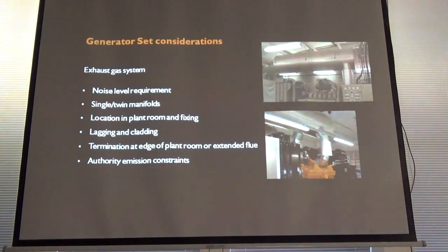Because again, at some point the cost comes into play. You don't want to give them something that's well over the top when a much more standard, smaller unit would suffice. But that comes into play more and more. The key distinction is portable units have much higher requirements on legislation, on emissions. The rationale behind that is they'll bang the portable units anywhere, they're on a site, they're not really getting rid of the emissions. If it's a permanent installation, like a plant room, like a high-rise building or whatever, then it's been considered, because you've got the exhaust flue that'll probably get to the roof and discharge it clear and away and disperse it, because the key thing really with the Clean Air Act is emissions dispersion, not control, but suitable dispersion really, where they consider local structures, where's the pipe, how it's directioned, and how it then clears.